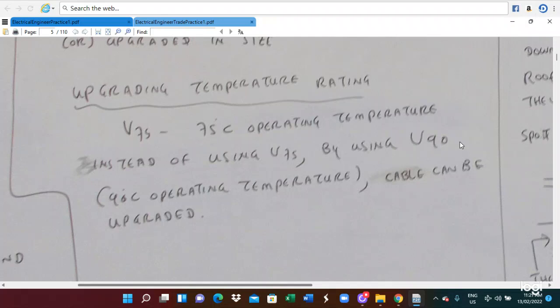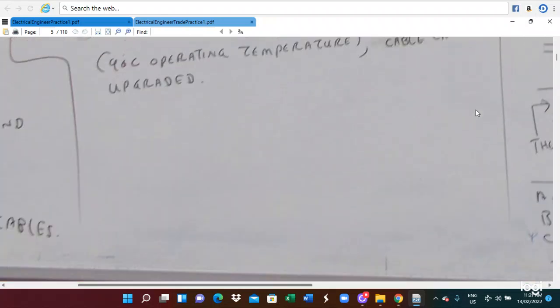One is that you can select a bigger cable using AS/NZS 3008, one step bigger cable, or you can upgrade the temperature rating. So instead of using 75 degrees centigrade, you can upgrade to V90. So these are the ways of cable derating, which is also an important aspect.